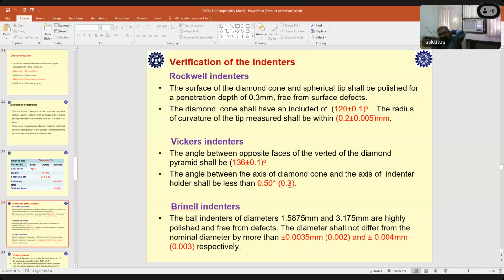Now, these numbers are all very, very critical. We may not be able to really appreciate how difficult or easy it is to make an indenter with this particular specification. Particularly if you want to establish a calibration machine, getting an indenter is not that easy. Even though you are able to establish a machine for the force component, and even if you have a measuring system, the indenter is the biggest challenge for a part 3 machine.